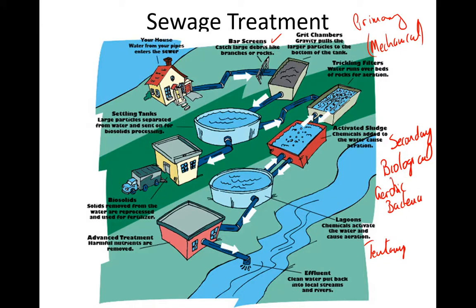So this is a decomposition phase where the aerobic bacteria are given plenty of O2, and by being given plenty of O2, they are fed, they're activated, and they go to town, decomposing and digesting any remaining sewage that is present in this particular water. And you can see that it's moved quite well, it's agitated quite well to keep the oxygen levels high, so that the aerobic bacteria can do what they have to do in decomposing the sewage that is present.